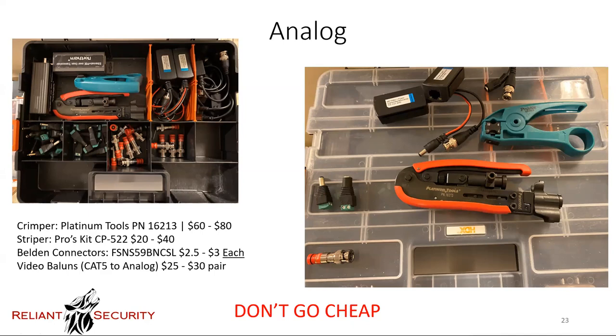Solid copper cable — I may have mistakenly said aluminum. Everything needs to be solid copper, especially on the power side. A lot of Siamese cable is actually copper-clad steel or aluminum — it's just an aluminum wire with copper painted on the outside. Any questions on the analog tools?